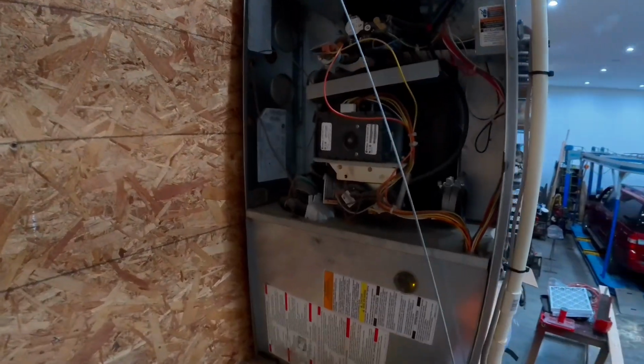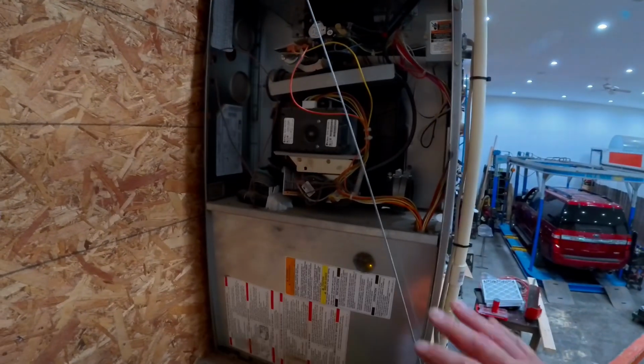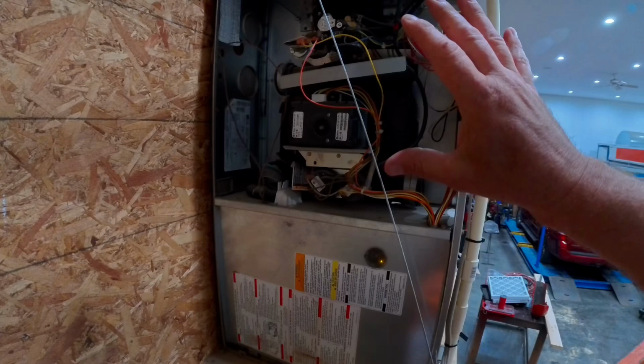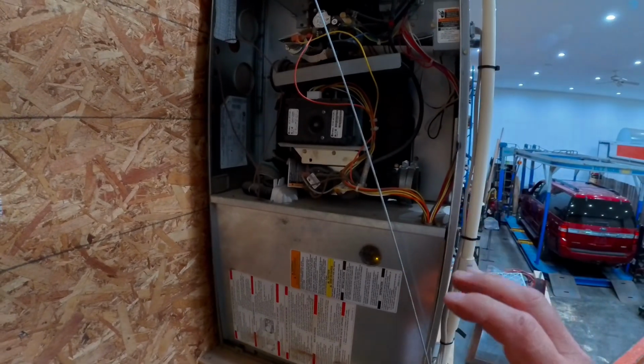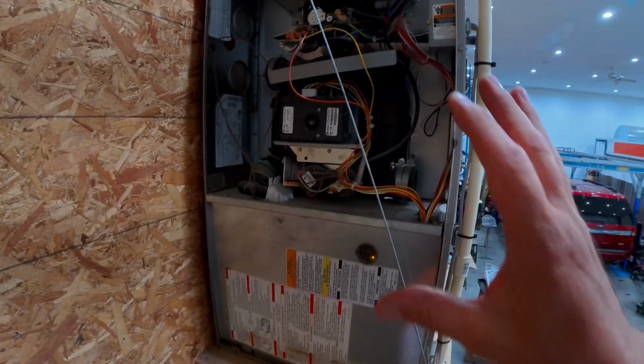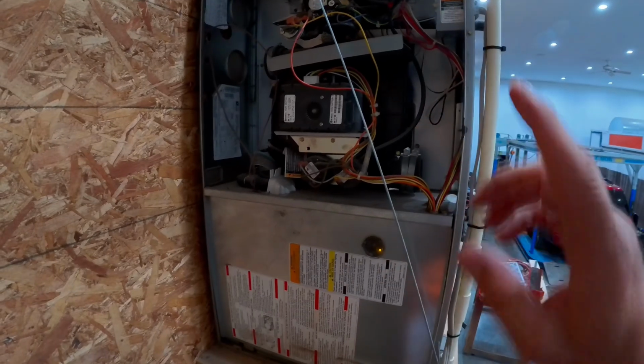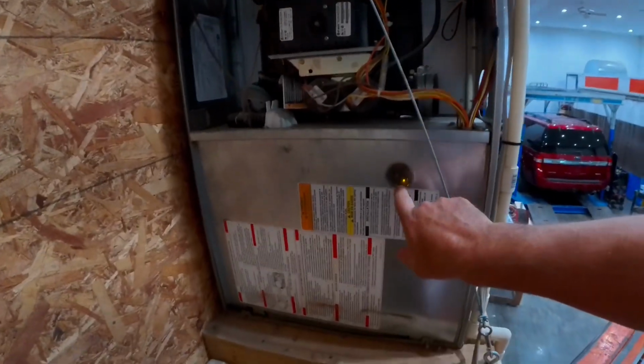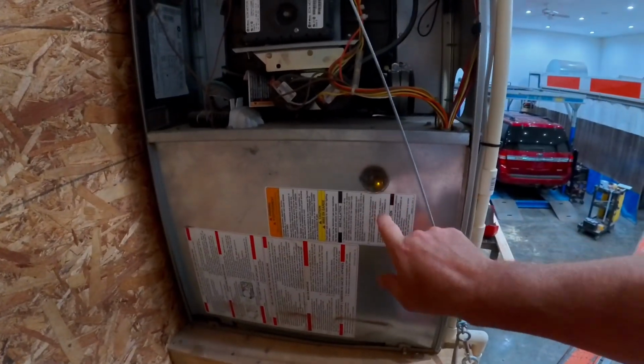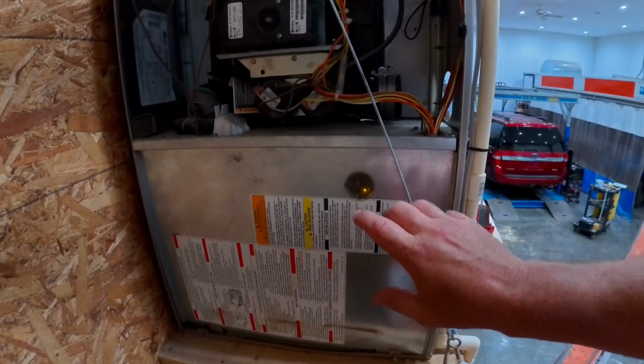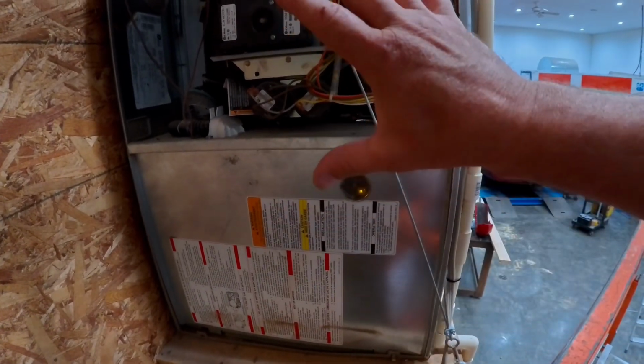So we're going to start our search right at the furnace itself. I've already got the front door taken off, as you can see, and basically my first check is: is there power going to my furnace itself? Now in this particular unit, I got a service light right down through this little glass screen right here. It's lit up orange. That tells me we at least have power to the unit.